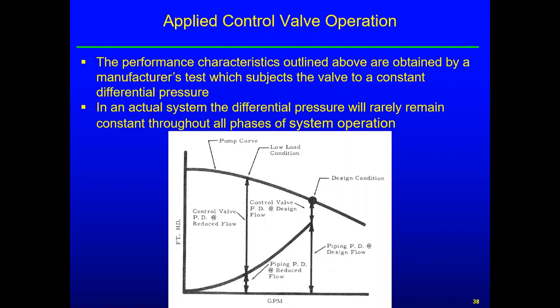In this diagram, they come up to the end of this curve at our design flow. And then we show just a straight line up to the pump curve, and that's the pressure drop across that control valve when it's wide open and the pump is delivering design flow to the system. And so the big dot, the design condition dot, is the operating point on the curve. So it's also possible to draw just one system curve that doesn't have this kind of discontinuity at the end, where you include the pressure drop of the control valve with the rest of the piping and the other components, in which case you just have a parabolic curve that goes from the design point down to the origin.